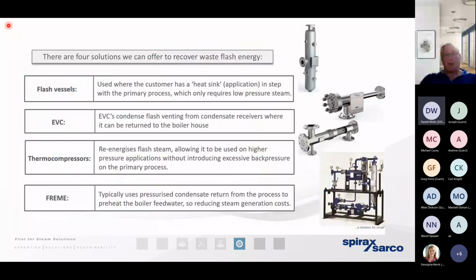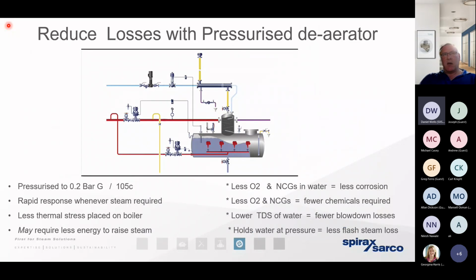So different solutions that we can use to make use of that flash steam can vary from the very basic flash vessels through to the more sophisticated and complex flash recovery energy management devices. It really comes from understanding the mass flow rate of condensate and the pressure drop that it undertakes. Once we understand that, the calculation's an easy one, and it's very easy to demonstrate what the payback is likely to be in financial terms. And one last solution that I'd like to discuss is by no means a new or futuristic solution, but it's one that perhaps isn't adopted as often as it should be here in the UK. It's what we call a pressurized deaerator.